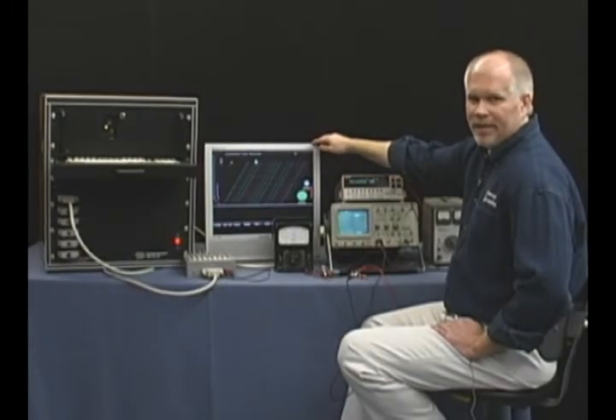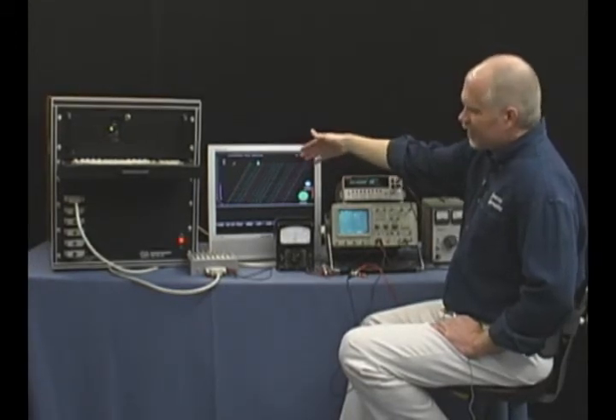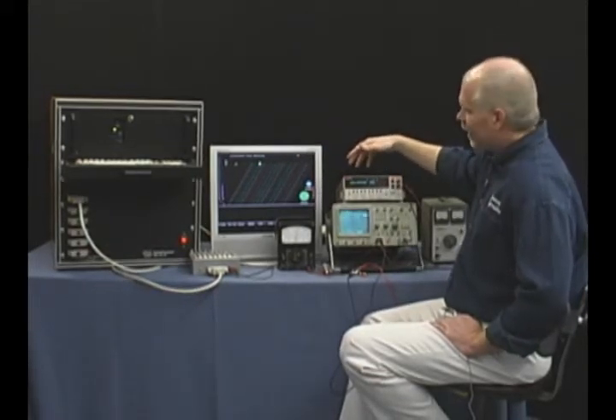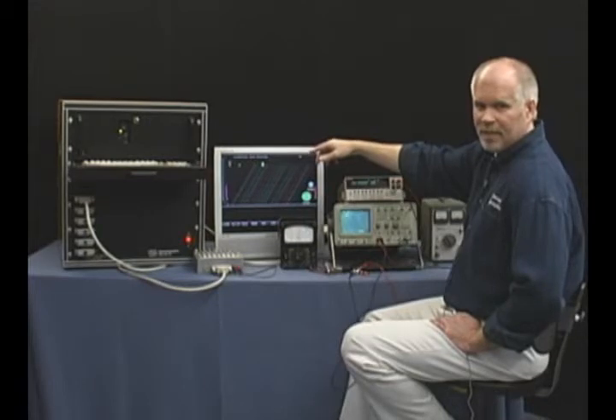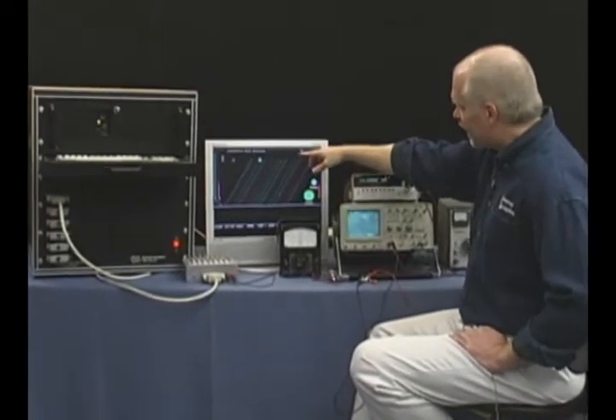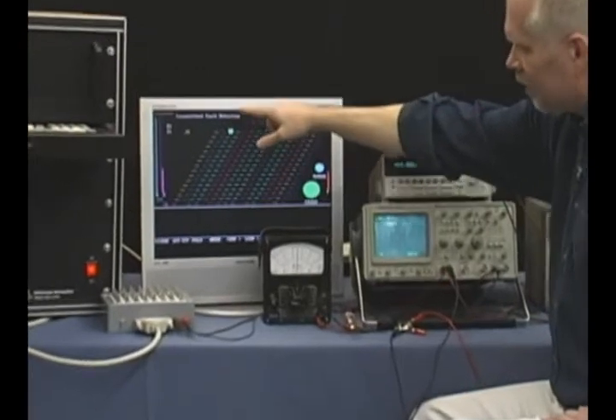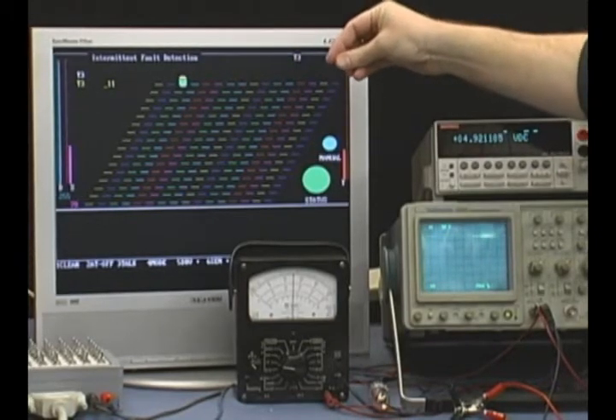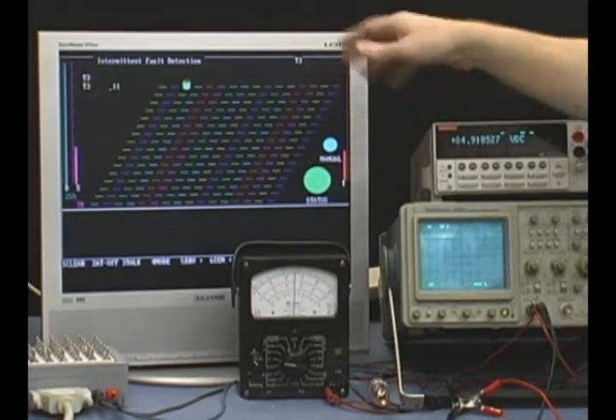To demonstrate this testing void problem, we've assembled a variety of instruments that are commonly used to test for and troubleshoot both hard and intermittent problems. One piece of test equipment that most of you may not be aware of is the IFD 3000 from Universal Synaptics. This tester is monitoring the same line as the rest of this equipment in parallel. The IFD 3000 can do an unlimited number of lines under test simultaneously and continuously. What you see on screen are 256 individual test points, and as it picks up an intermittent, you'll see a column grow on the affected test point line. You'll also hear a synthesized voice telling you in your own terminology what that line is, based on a map file you create.